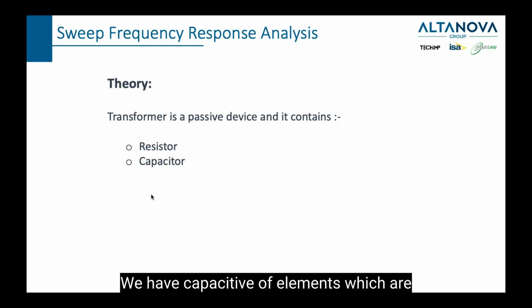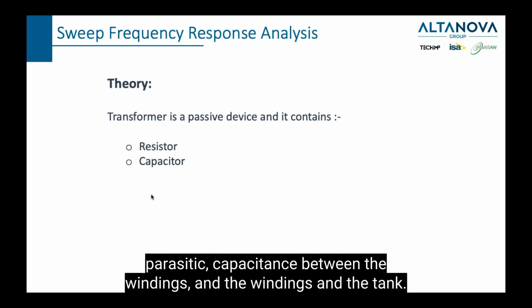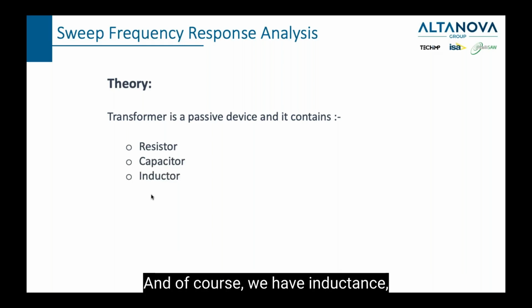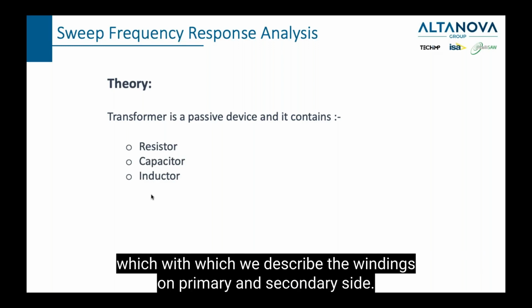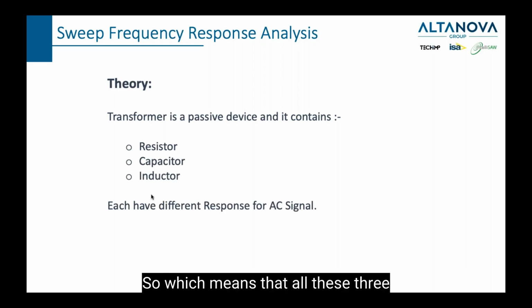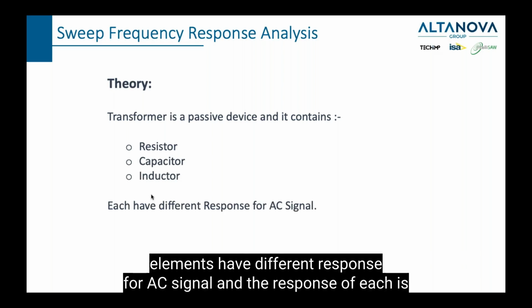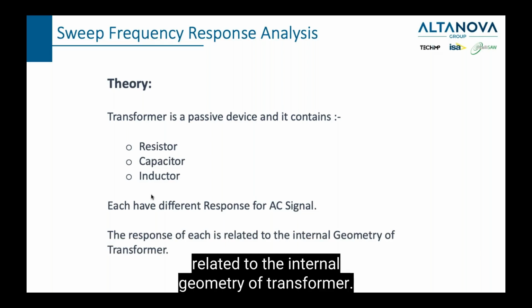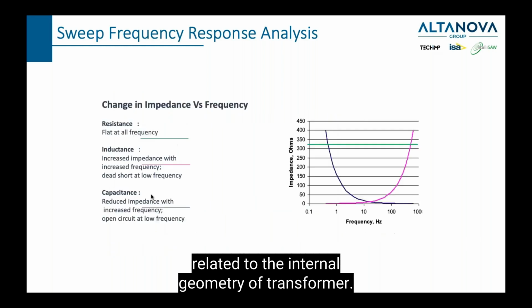We have capacitive elements, which are parasitic capacitance between the windings and the tank. And of course, we have inductance, with which we describe the windings on primary and secondary side. Which means that all these three elements have different responses to an AC signal, and the response of each is related to the internal geometry of the transformer.